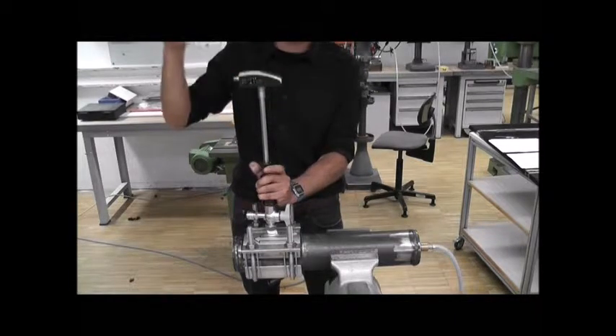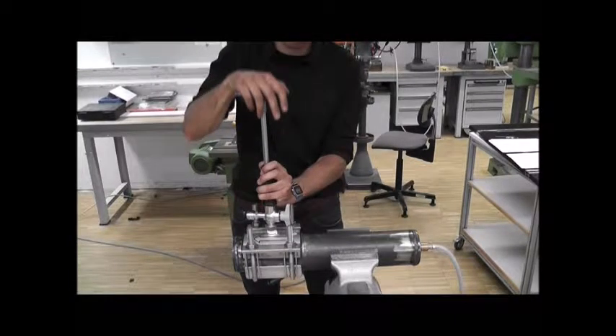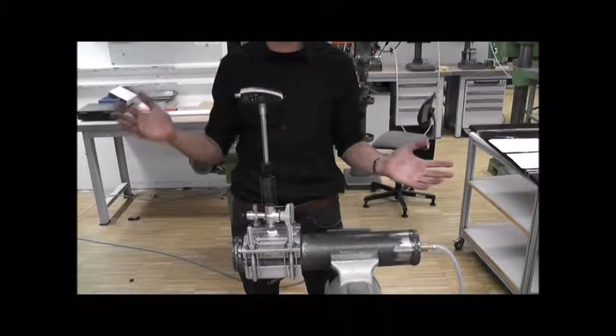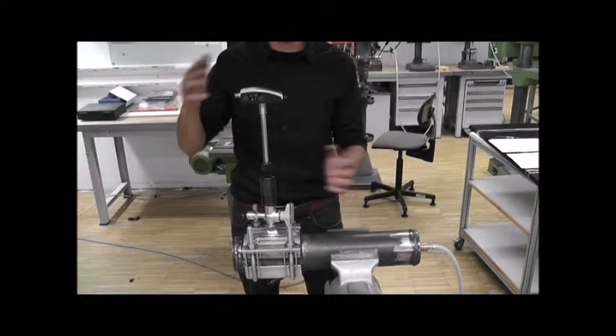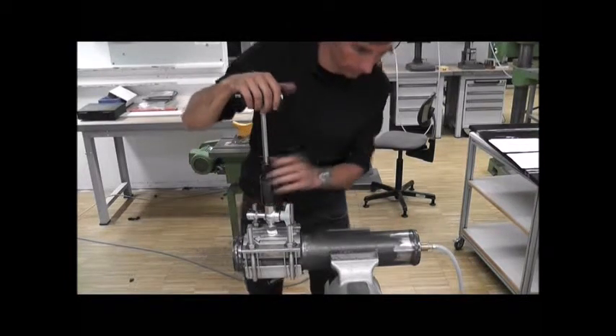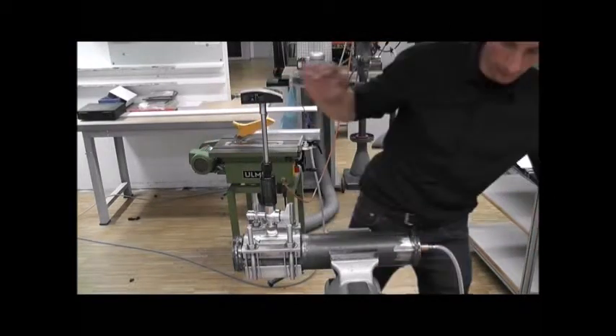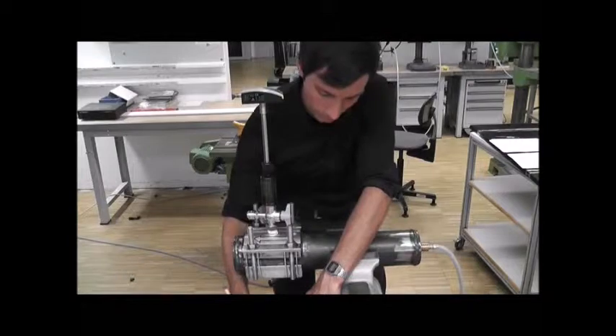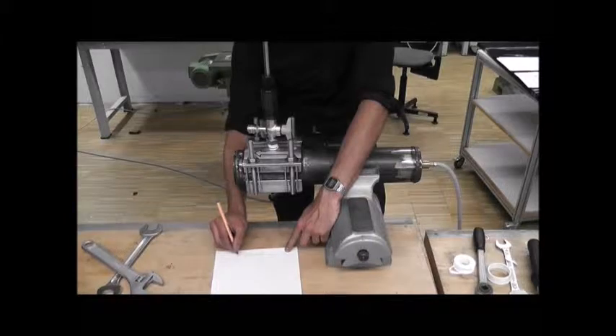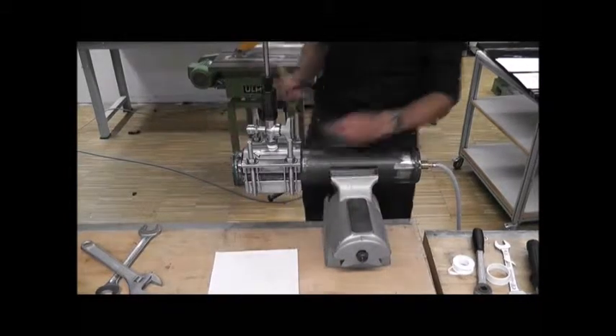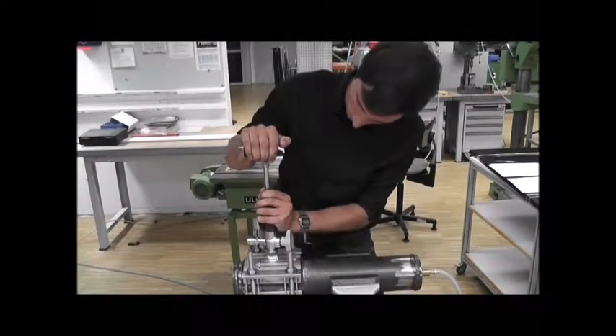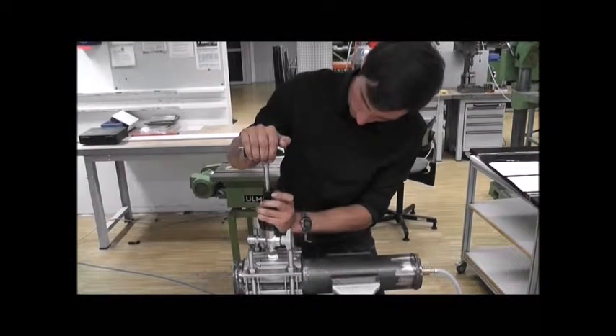If you remove the pressure of pressing, you'll see the transmitter will not kick back. That's a big advantage compared to our competitors. The reason why the transmitter does not kick back is related to the recoil protection. Now we have to adjust the transmitter to the middle of the pipe. To do that, add the outer radius of the pipe to the scale you assigned before and adjust the transmitter to this value. Now the transmitter should be on the middle of the pipe. After the adjustment of the 6448, screw the scale of the transmitter tight.